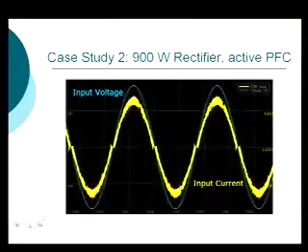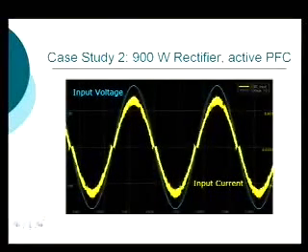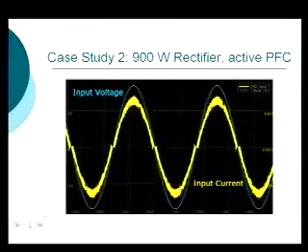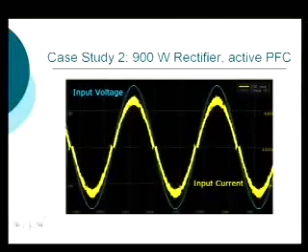Regarding the bandwidth of the fast current loop: since it's a hysteresis current controller, it should theoretically work at VTB's time step. The outer voltage loop is something like one hertz — it's really slow. From a control system standpoint, you want the inner current loop at least a decade faster so you don't have interactions between the two loops.